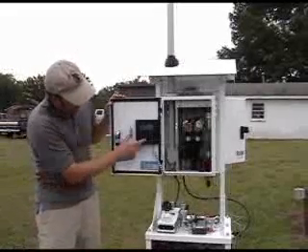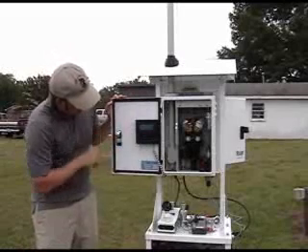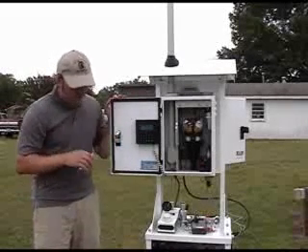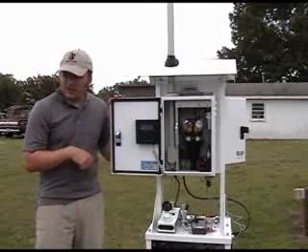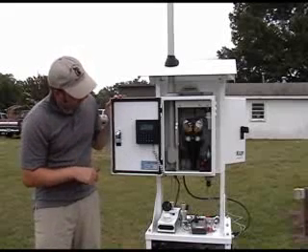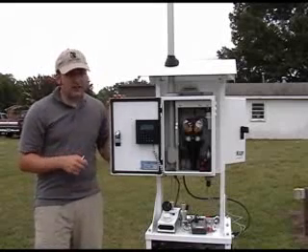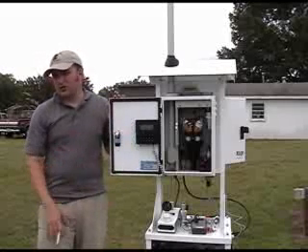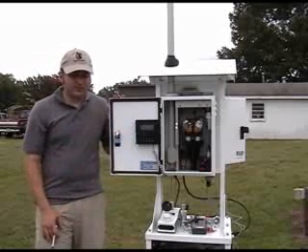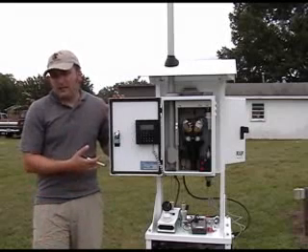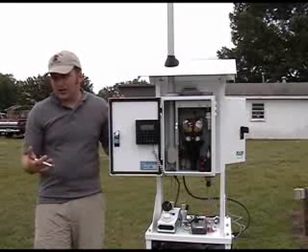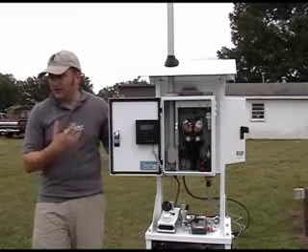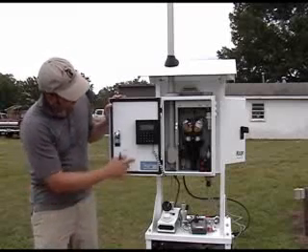So I'm going to scroll down using F4. Our next options are calibration, maintenance, and audit. We're going to make extended use of calibration and audit today. We'll go to set up the instrument. Maintenance has a couple things, like you can manually turn on and off solenoids of the pump, just general troubleshooting. You probably wouldn't go into that menu unless you're on the phone with RTI or URG troubleshooting something. They ask you to go in and check something out.